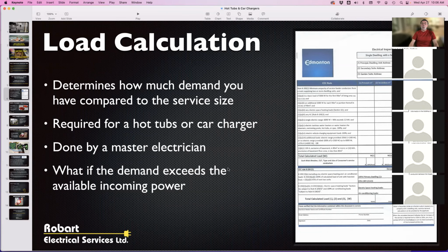What you want to do is ensure you do not exceed the rating of your service. Let me tell you what that means. If you've got a 100 amp electrical service—and in your home, you can tell if it's 100 or not by looking at the end of the handle on the main breaker, that breaker on the very top of the panel above all the rest. It's a double breaker, and on the end of the handle it'll have the number. Normally, if you've got a house after 1965, it's going to be 100 amp. Today, a lot of builders are putting in 200 amp and so forth, but the typical one you're going to find is 100.